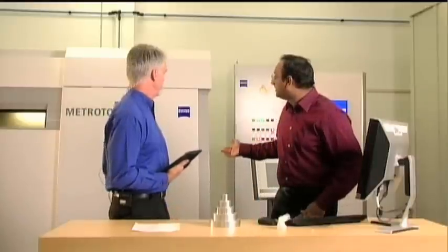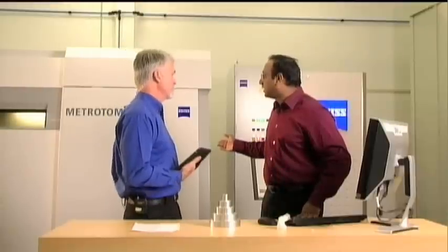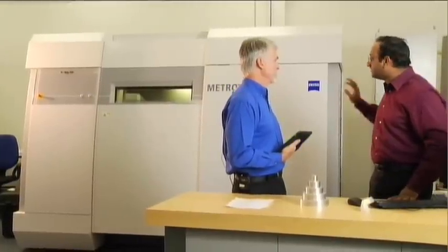I got another question here, also from William. He says he has a small facility and no real place to put a separate piece of equipment. Does this need to be in a special room? Is the X-ray technology safe? As you can see, it comes with a nice clamshell design. It's well protected. It's got a lead cover that protects the X-rays from escaping. It is built according to the standards that the FDA requires for all X-ray systems.